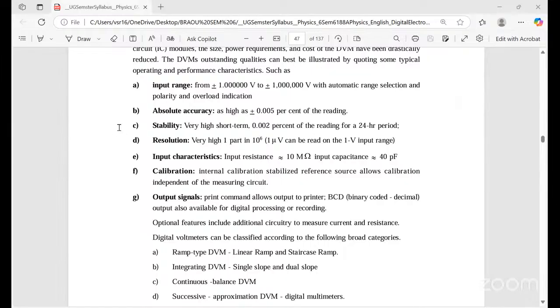What is the absolute accuracy? Plus or minus 0.005%. Stability is also very high, 0.002% of the reading for a 24-hour period. Resolution is also very high, 1 part in 10 to the power 6. Input resistance is approximately 10 megaohms, and input capacitance is 40 picofarads.